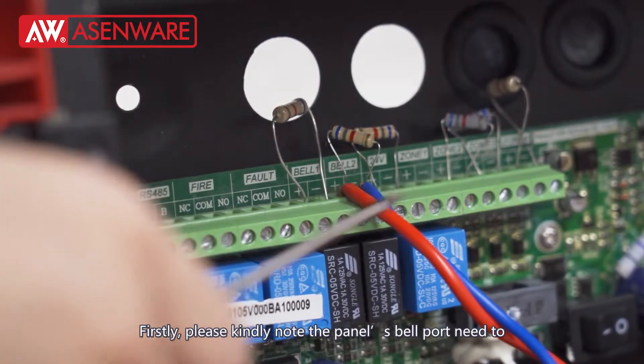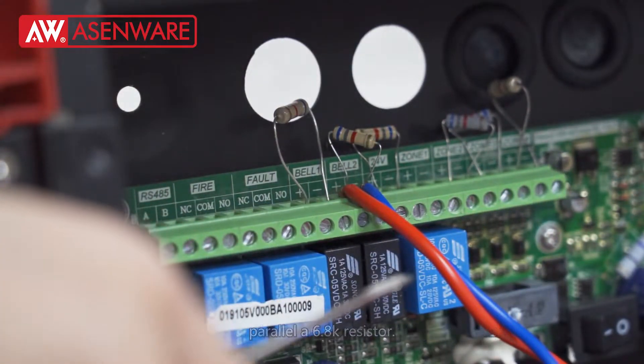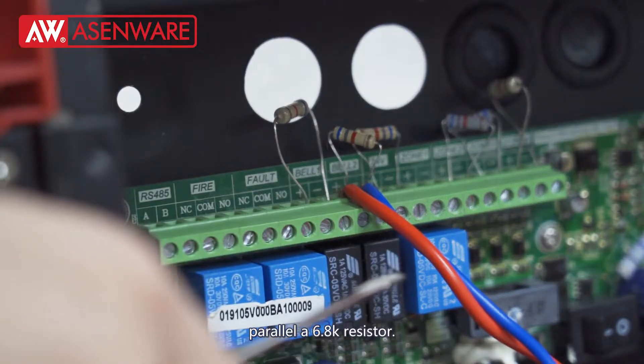Firstly, please kindly note that the panel's bell port needs to parallel a 6.8K resistor.